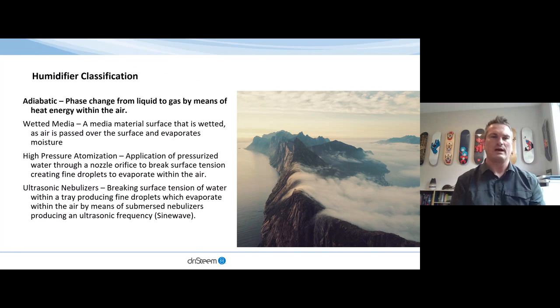The benefit of an adiabatic process is that because it's utilizing the heat energy from the air, it has a cooling effect. We've all heard of swamp coolers. We've all been to restaurants or bars or other places where outdoor misting systems have been applied to cool the air around us. And this is the same effect. About 1,163 BTUs of heat energy, roughly, depending upon the temperature of the air, is utilized for every pound of water that's absorbed. So in essence, we are getting a temperature drop from that. If you're looking for ways to supplement the cooling of a building or the environment, adiabatic may be a viable option to consider.